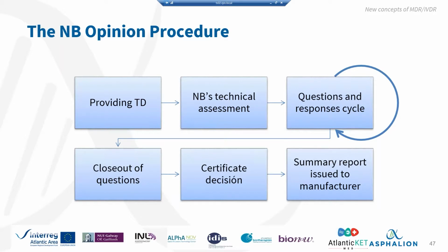And then the process will enter a questions and responses cycle, which means that the notified body may ask for clarification on certain points, and the manufacturer will have to provide answers to the questions of the notified body. This is an iterative process, so it can happen many times. It will be limited only by the will of the notified body.